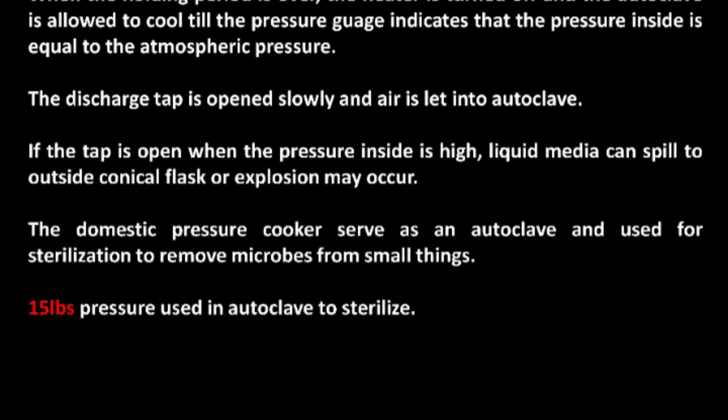When the holding period is over, the heater is turned off and the autoclave is allowed to cool until the pressure gauge indicates that the pressure inside equals atmospheric pressure. The discharge tap is opened slowly and air is let in. If the tap is opened when the pressure inside is still high, liquid media can spill out of conical flasks or an explosion may occur.